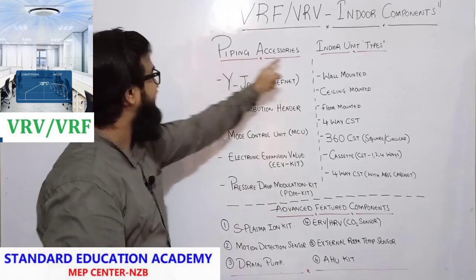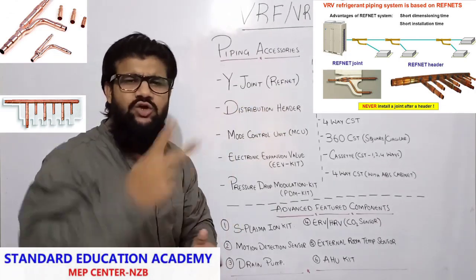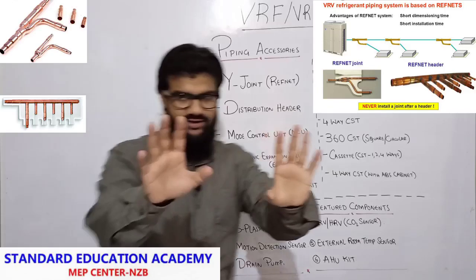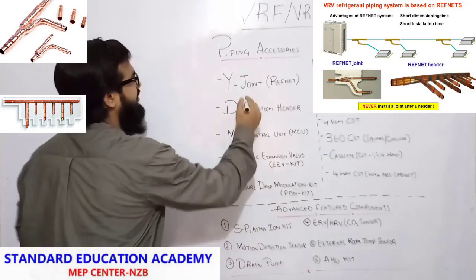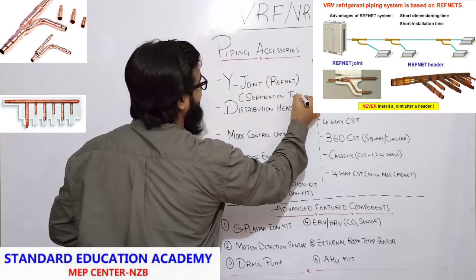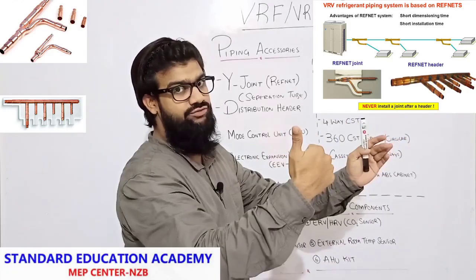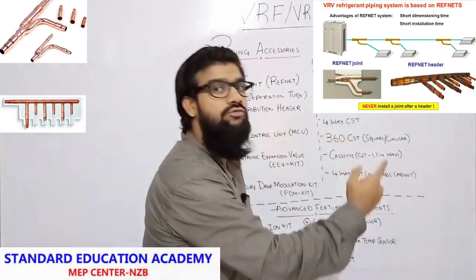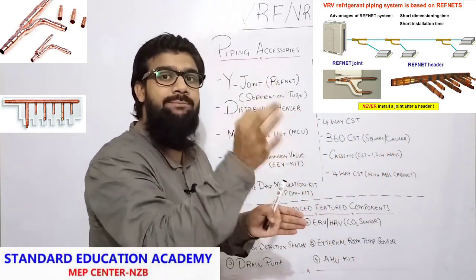The first accessories are piping accessories — what accessories will we find in the piping of a VRV system. First is Y joint, also called a REFNET joint or separation tube. Two types of connections are there in piping: one is Y joint, the other is distribution header. Keep in mind: separation tube should always come before the header. Always place a separation tube first; next, at the end of the pipe, go for the header. Because after the header, you cannot place a separation tube in a VRF VRV piping system.